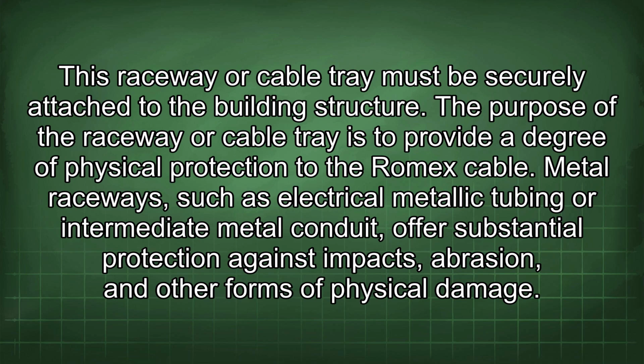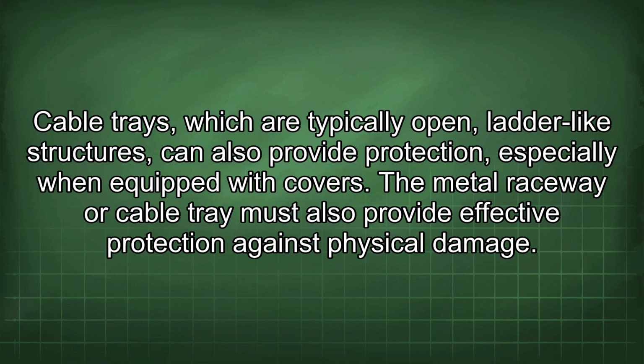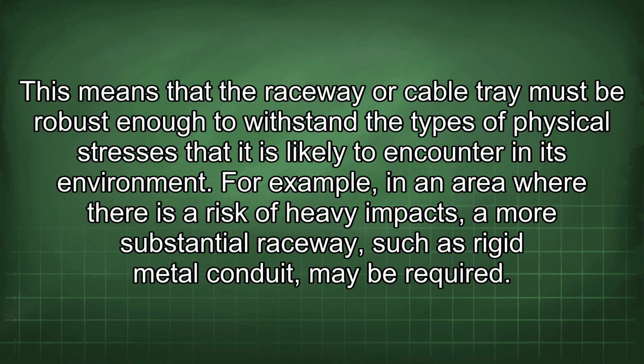Metal raceways, such as electrical metallic tubing or intermediate metal conduit, offer substantial protection against impacts, abrasion, and other forms of physical damage. Cable trays, which are typically open, ladder-like structures, can also provide protection, especially when equipped with covers. The metal raceway or cable tray must also provide effective protection against physical damage. This means that the raceway or cable tray must be robust enough to withstand the types of physical stresses that it is likely to encounter in its environment. For example, in an area where there is a risk of heavy impacts, a more substantial raceway, such as rigid metal conduit, may be required.